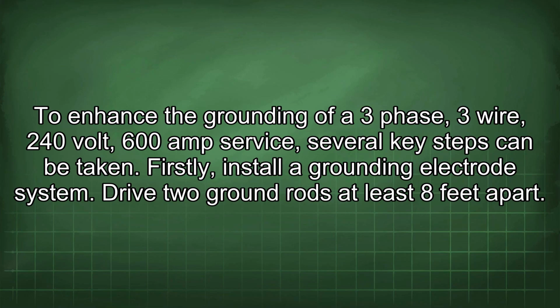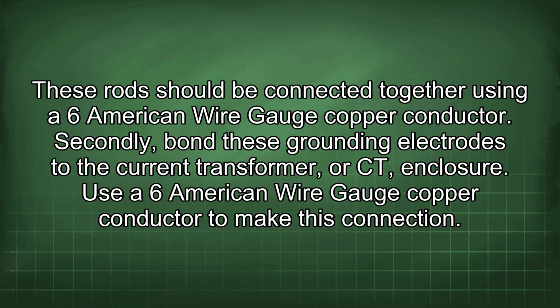To enhance the grounding of a three-phase, three-wire, 240-volt, 600-amp service, several key steps can be taken. Firstly, install a grounding electrode system. Drive two ground rods at least 8 feet apart. These rods should be connected together using a 6 American wire gauge copper conductor.